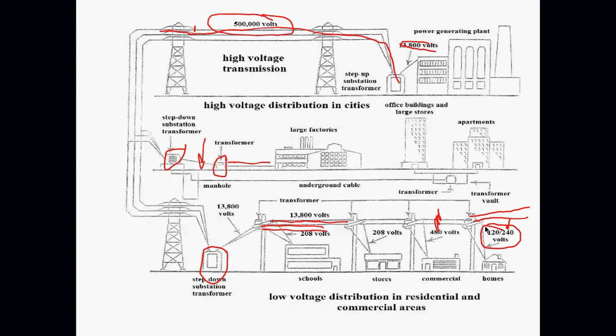Okay, this is why if the pole gets hit with lightning, if you take a lightning strike on the wires, it can actually travel through neutral if things aren't grounded properly. Happens quite a lot. Grounds go bad over time. People pull grounding straps. People pull grounding rods. It happens. So that's why I say never trust neutral. You do not know what is grounded and what is not, so you always have to test it.